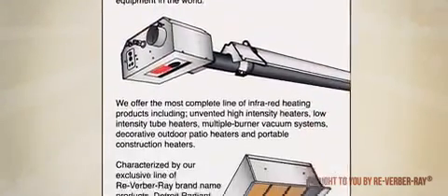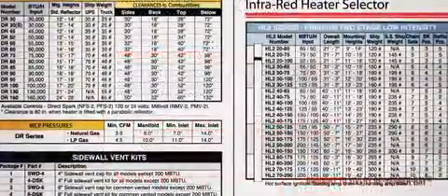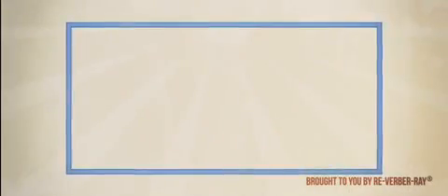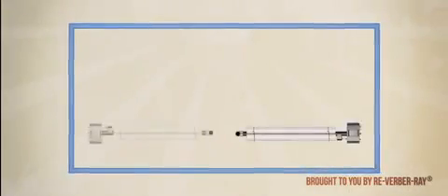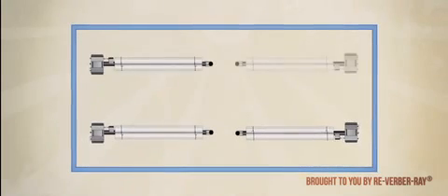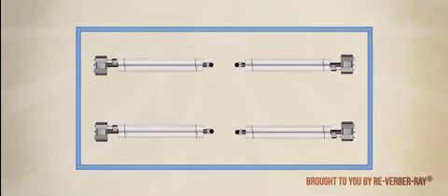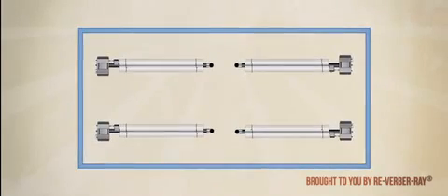Once the total heat load has been calculated, the type of infrared heater that best suits the application and the quantity required to offset the calculated heat load can be determined. As a rule, multiple heaters of lower BTUs are preferred over single large BTU models. However, heater selection is generally based on the available mounting heights and clearances where the heater will be located.